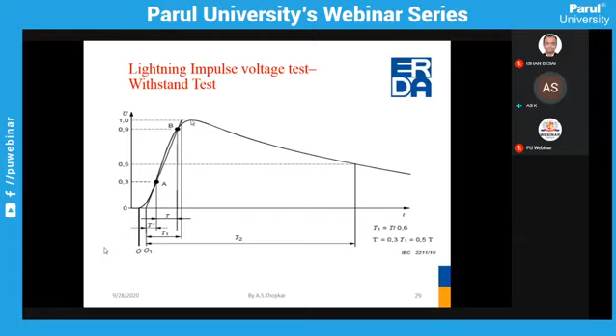Similarly, this is the peak value, and this is T2. T2 means the time required to reach 50% of the peak. Here it is mentioned as 0.5. So these three parameters we have to maintain. 1.2 is the front time, 50 microsecond is the tail time, and the peak magnitude, like 75, 145 or 275 as I have shown in the table, we select from the table depending on the voltage rating. So the test voltage depends on the voltage rating.